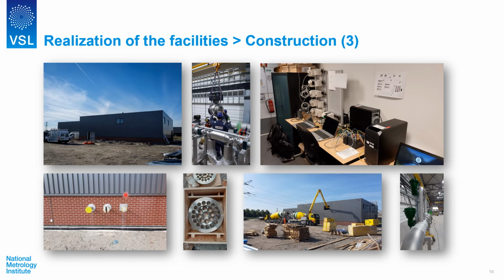You can see the outside connections because we can also calibrate meters on small trucks if that's needed. Of course, you have seen the construction of the master meter section, and to make sure that an ultrasonic or turbine meter from a customer has a nice, correct flow profile, we use these conditioning plates. Here's some other pictures of concrete being poured into the building, and here's some control valves on the WF2500 system.